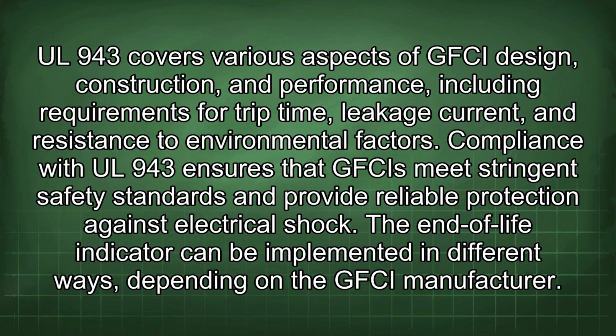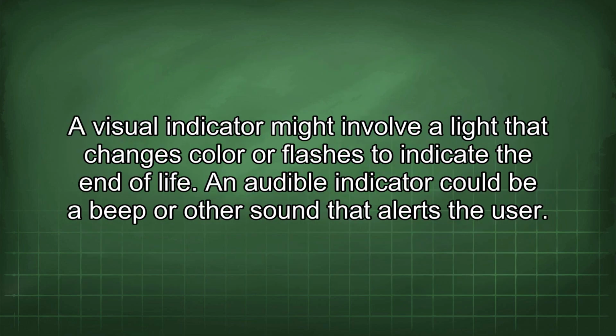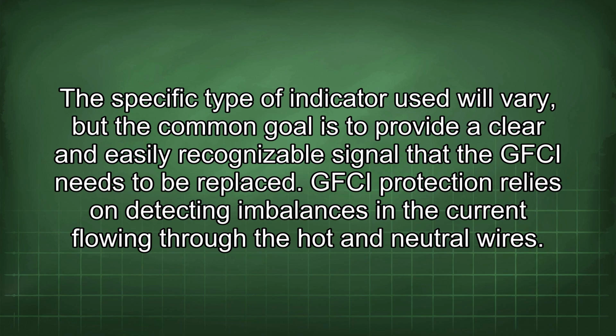shock. The end-of-life indicator can be implemented in different ways depending on the GFCI manufacturer. A visual indicator might involve a light that changes color or flashes to indicate the end of life. An audible indicator could be a beep or other sound that alerts the user. The specific type of indicator used will vary, but the common goal is to provide a clear and easily recognizable signal that the GFCI needs to be replaced.